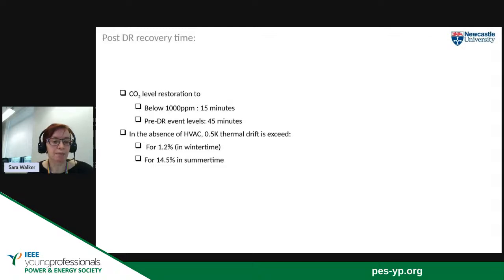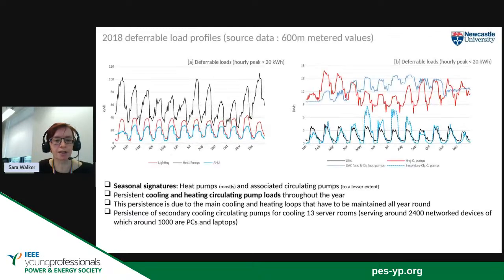Our carbon dioxide demand response event potentially depends upon the nature of the space, but sometimes we can be offering demand response and recovering the carbon dioxide levels fairly quickly. So we can get back below 1,000 parts per million after 15 minutes of the air handling units being back on, and to get back to whatever level it was before the demand response, about 45 minutes. And I mentioned those heating 1.2% of the year were slightly outside of comfort conditions, and for cooling, about 14.5% of the time were slightly outside of comfort conditions.